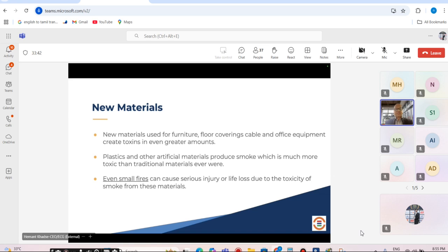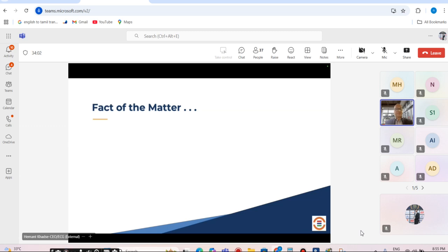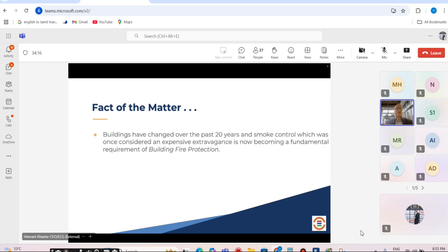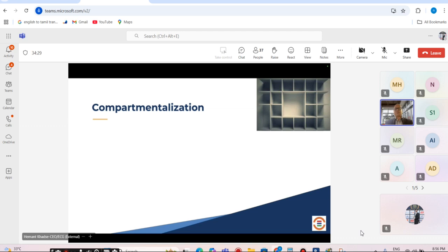So are these materials going to comply with the properties of not generating smoke, and also having flame resistive properties? And this is part of your passive fire measures. The architect is usually supposed to look after it, but somebody has to evaluate, and it's the job of a life safety engineer to look at whether it is ensured or not. So things have changed very, very much in the last 20 years specifically, where smoke management is becoming very evident when it comes to building design.